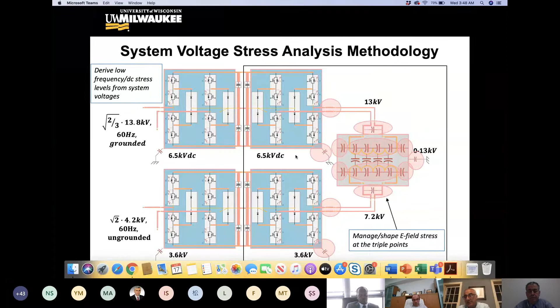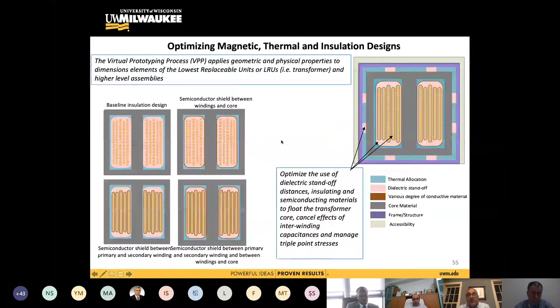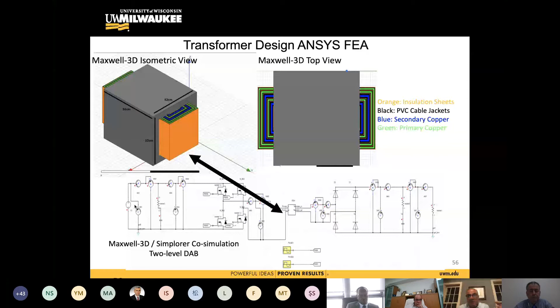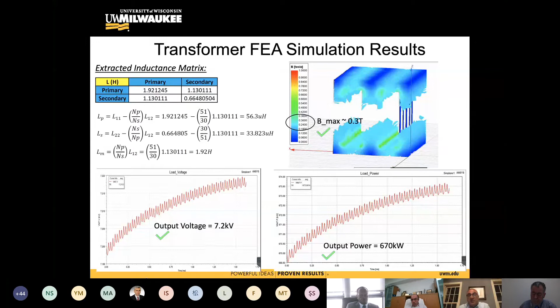You have to look at all the leakage capacitances, and those leakage capacitances are going to introduce EMI currents that are going to, of course, have common mode noise, and you're going to have a lot of issues with noise at 13 kV DC and 20 kilohertz. So all those capacitances must be identified and reduced in the system. With that, you get the transformer design. And for this transformer, again, the size is not significant, but the power and voltage are really significant. We go through multiple stages of the design, as I mentioned, looking at the flux level, whether you can control the power, and what the leakage inductance of the system is going to become.